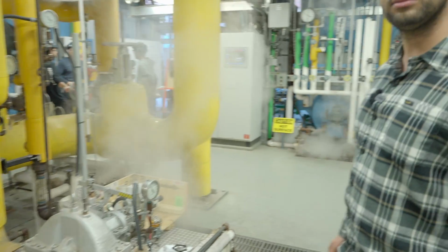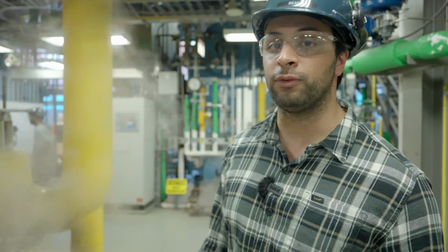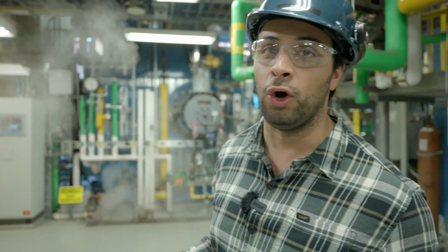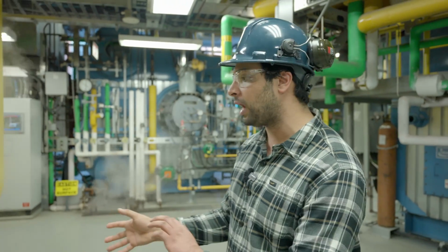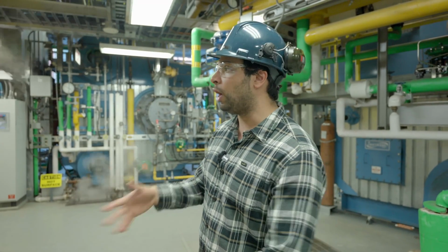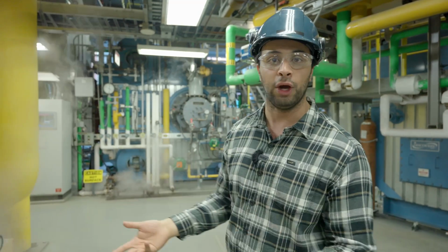How do you manage the condensate? One of the ways we do it is right from the beginning. Once we get the boiler up and running, like this morning we were stone cold. There was no pressure in the header, no pressure in the boiler. So what we do is we open up all of the bypass valves for the steam traps. We open those up, we open our non-return valve on the boiler, and we just let steam start to flow through all the systems.